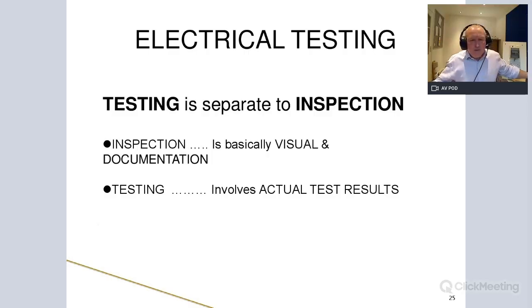So for instance, if you drop a socket - and you wouldn't drop every socket, you do a percentage of them - you're looking closely: are the cables terminated correctly? Is there any copper showing? Are they in the right terminals? Is it the right size cable? Those are the things you're looking for when you're inspecting somebody's work. It's a whole list of them.